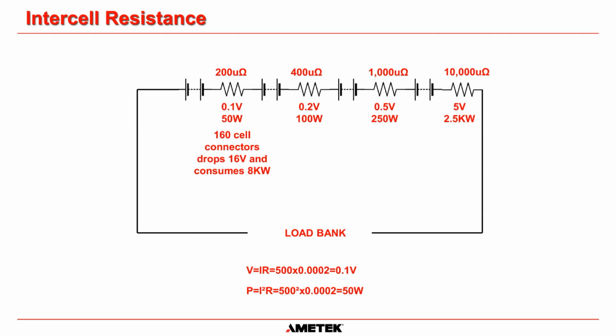So if the resistance of the connection was 200 microohms, that's going to drop an additional 0.1 volts across each of those connectors. And in that previous battery, there was approximately 160 cells. So that means across the whole battery, 16 volts is going to be dropped across those connectors. But more importantly, 8 kilowatts of power is going to be dissipated across those resistances. Those connections are going to start to heat up and dissipate power.